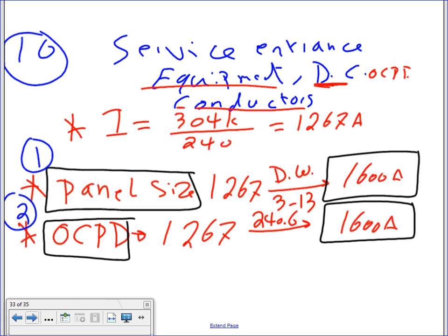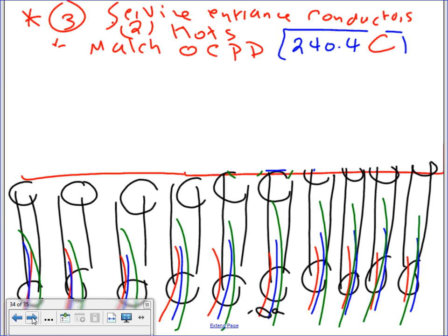Now tomorrow, guys, for that test, how are you going to size your panels for me? Make them the same as the overcurrent protection device. Just match them. They don't always have to match. For now, the panel size and overcurrent protection device go to 240.6. Let's go back down into the conductor size. Now for the conductor, 240.4(C), guys, match the overcurrent protection device.